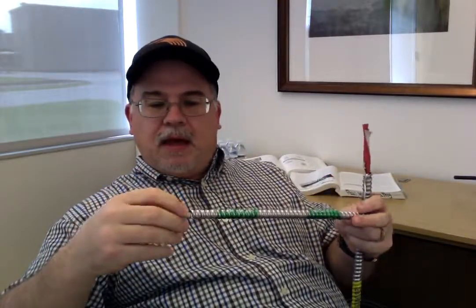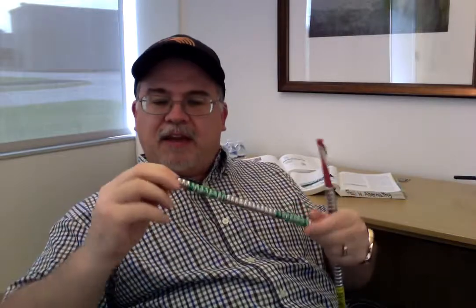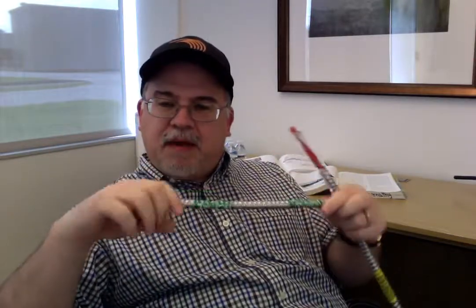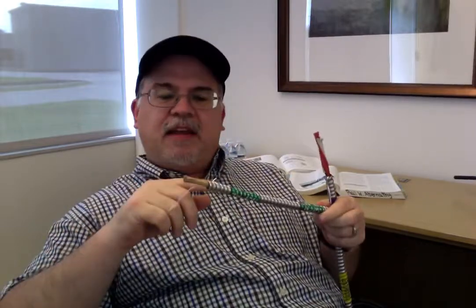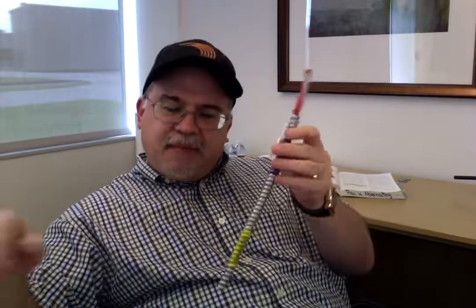That would happen because the diameter of this armor corresponds to the allowable diameters for this connector. And if you put this 10 gauge against it or wrap it around the armor, you're changing the OD of the actual armor, and this connector will not fit properly. And it was never listed for that type of application. So this is not the same as when you're using a product like this, which just happens to be an AC cable. And you'll notice with the AC cable, it's got a little 16 gauge wire that actually can bend back and sit neatly inside of the interstices of the actual armor, which won't inhibit the connector. You can't say the same thing for an MC cable.